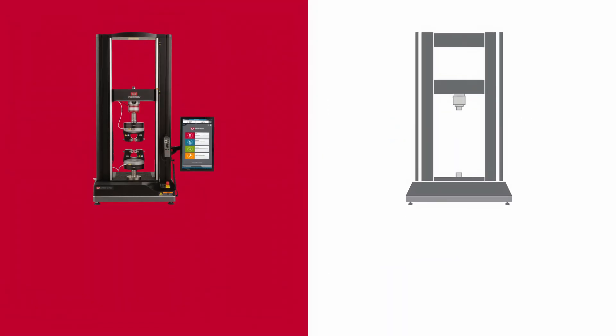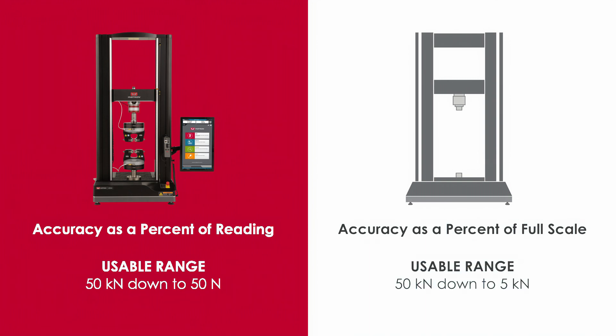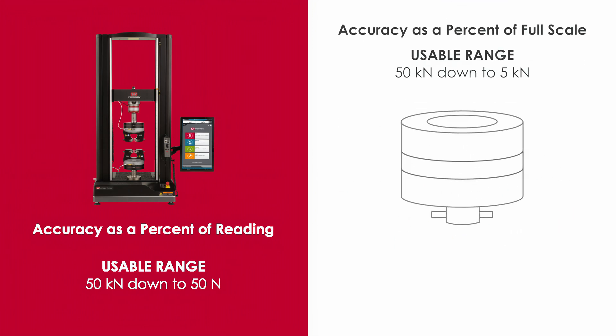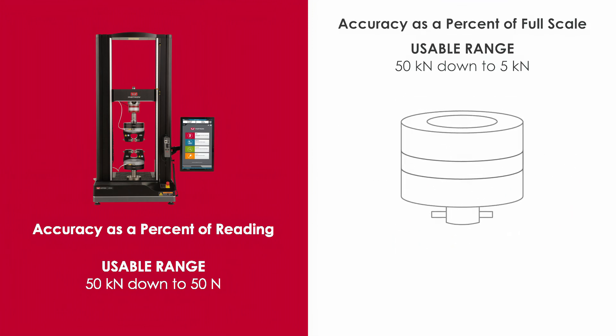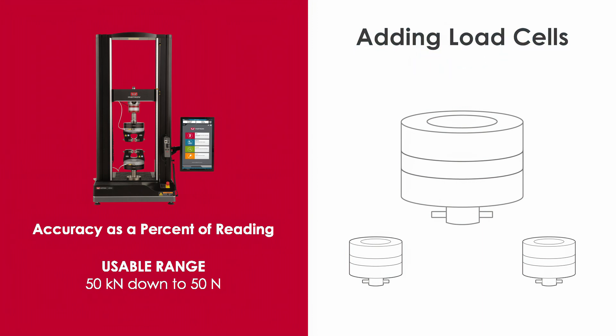To recap, our first setup using accuracy as a percent of reading had a usable range of 50 kilonewtons down to 50 newtons. In our second setup, using accuracy as a percent of full scale, the usable range was 50 kilonewtons down to 5 kilonewtons. As you can see, the usable range of a load cell using accuracy as a percent of full scale is more limited, which means with other suppliers you may need to purchase multiple load cells if you plan to test below 5 kilonewtons. Adding load cells not only increases expenses, it also adds complexity to your lab.